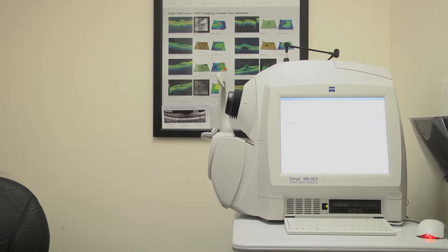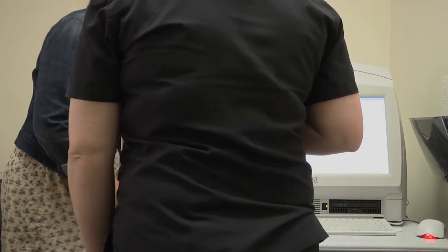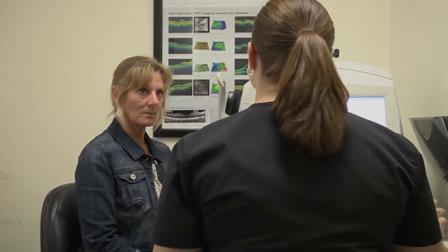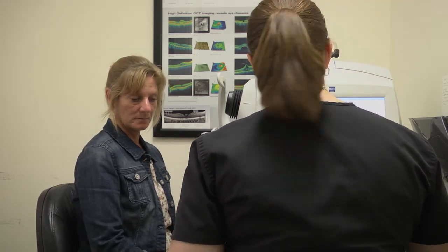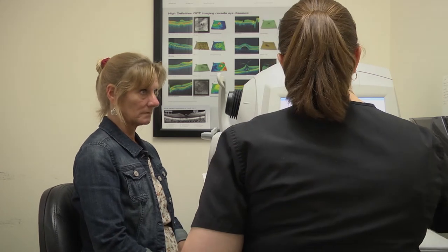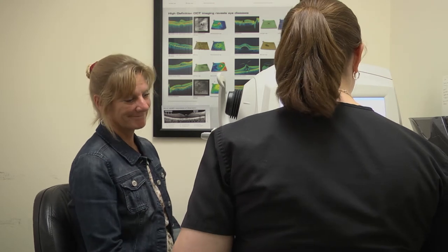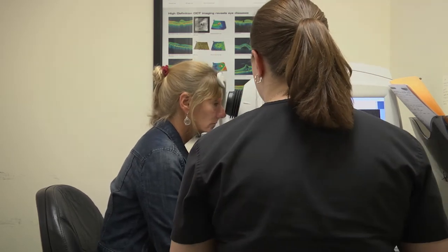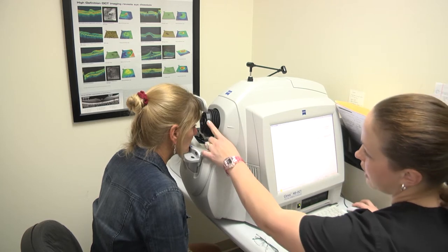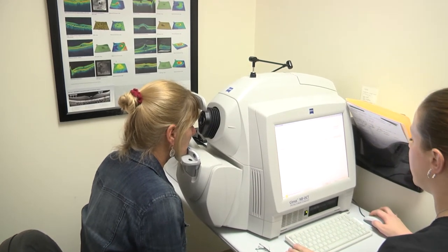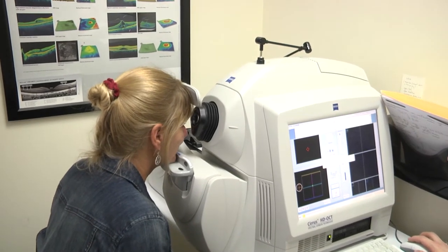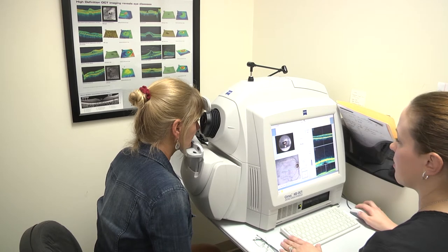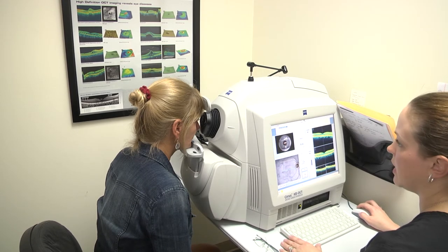Now you're going to perform an OCT test, also known as an optical coherence tomography. This test will measure the patient's optic nerve, retina, and macula. Make sure to check with your doctor what tests they want done. Walk the patient into the room, have them take a seat, and enter their information into the machine. Once the information is in, instruct your patient to come forward to the chin rest, forehead nice and tight against the head rest. Have them focus on a green star, looking directly in the center. At this point, hit the button Optimize — this will bring everything into focus. Once you're happy with your image, ask the patient to blink several times, then press Capture.